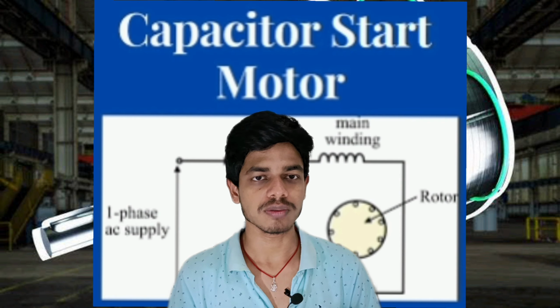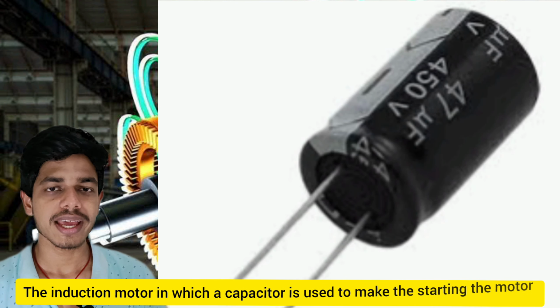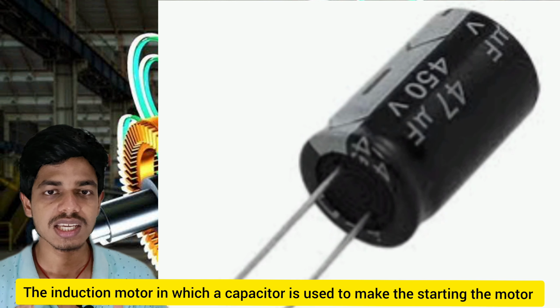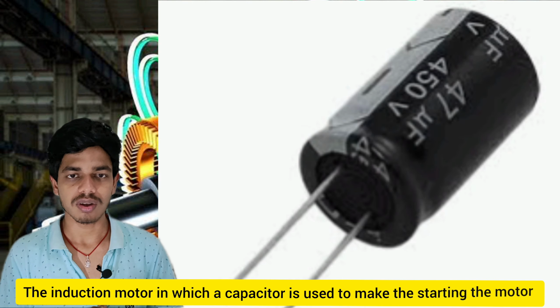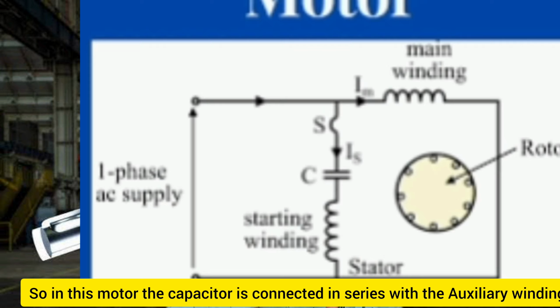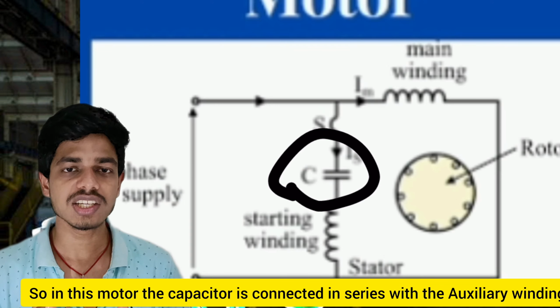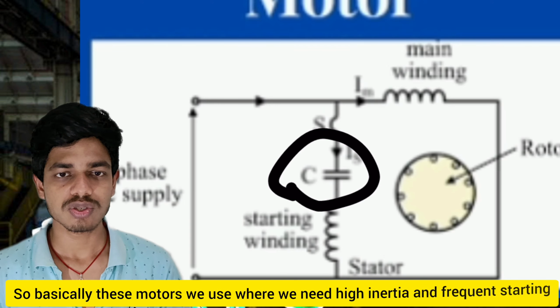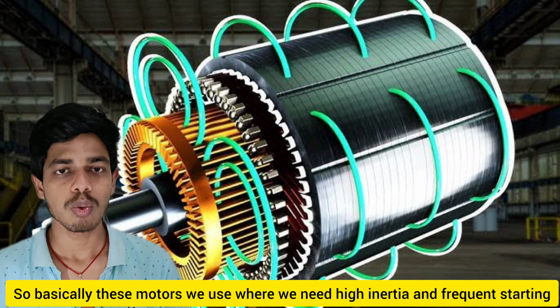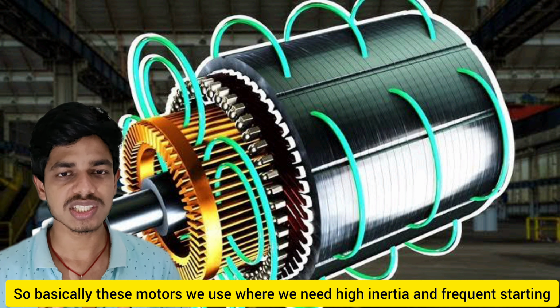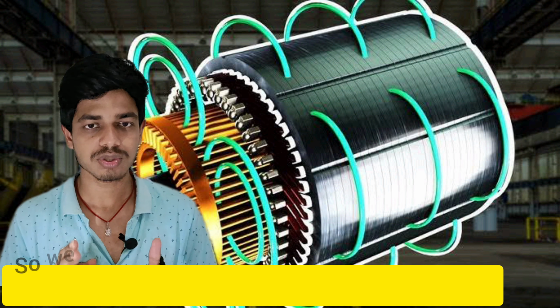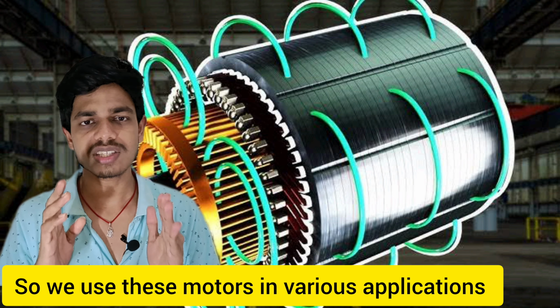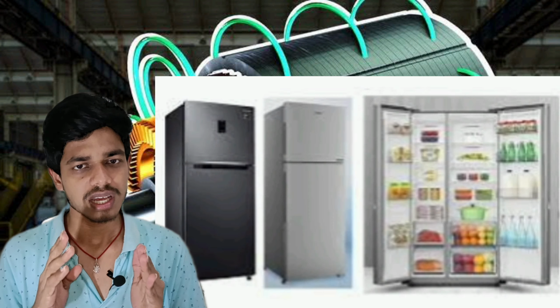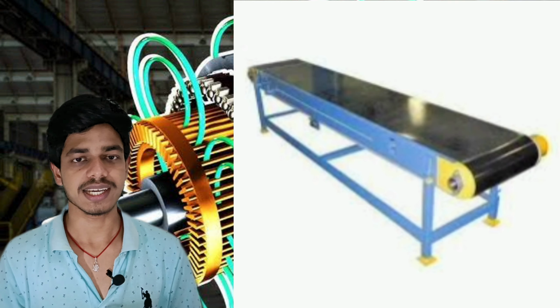Now we discuss the capacitor start induction motor. The induction motor in which a capacitor is used to start the motor is called a capacitor start induction motor. In this motor the capacitor is connected in series with the auxiliary winding. These motors are used where we require high inertia and frequent starting. We use these motors in various applications like compressors, refrigerators, conveyors, etc.